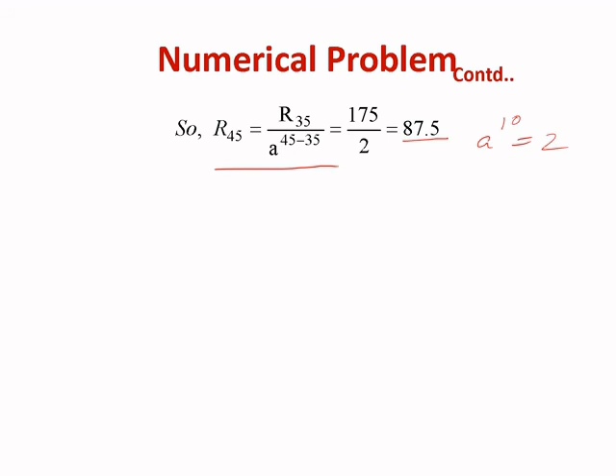So the equation is R45 equals R35 divided by A to the power 45 minus 35. R35 is 175, and we already have A to the power 10 equal to 2. If you replace A to the power 10 with 2, R45 equals 87.5 mega ohm, but mind that this 87.5 mega ohm corresponds to a 100 meter length of the cable. But in this problem, they want to know the insulation resistance at 45 degree centigrade corresponding to a 50 meter length of the cable, which means the length is half.